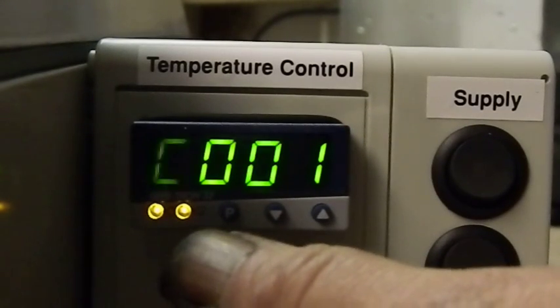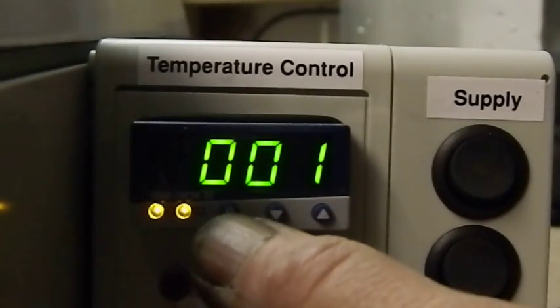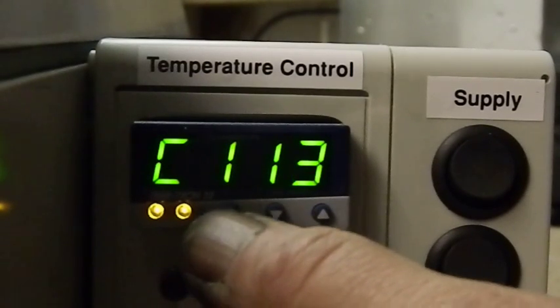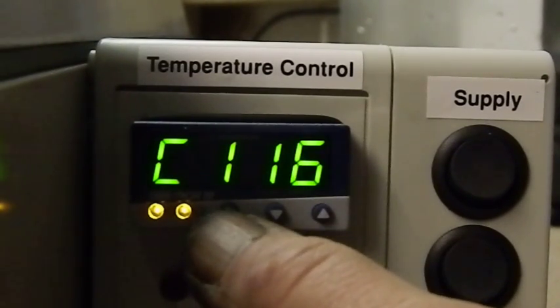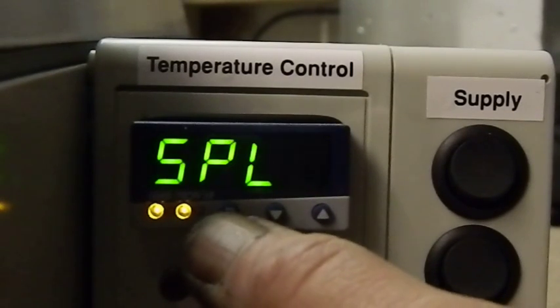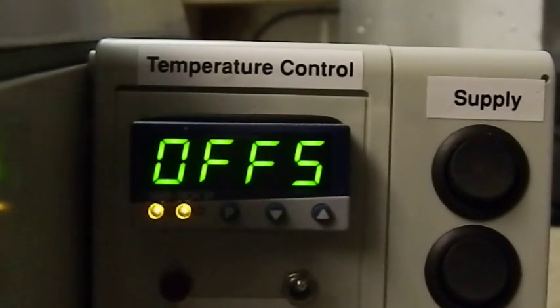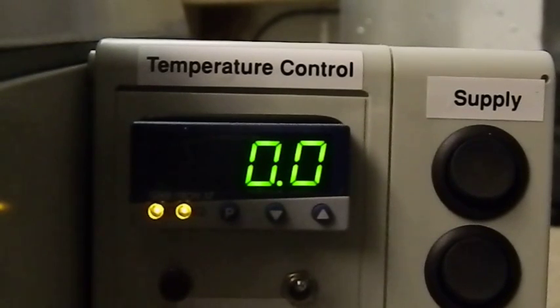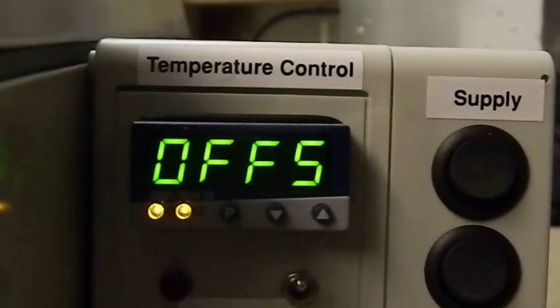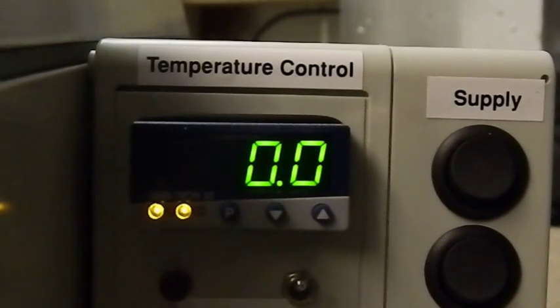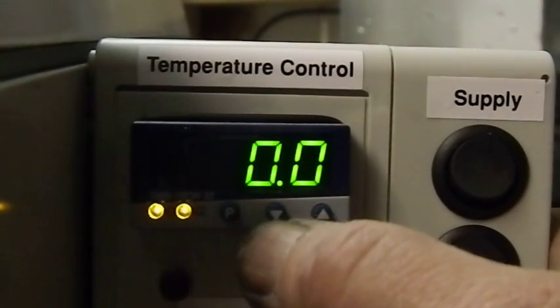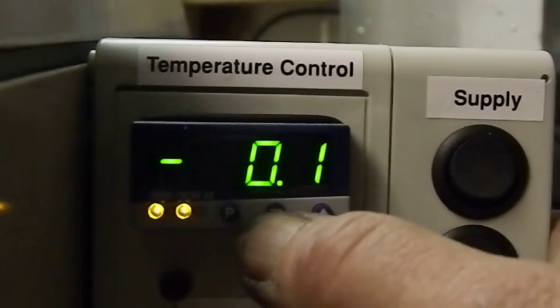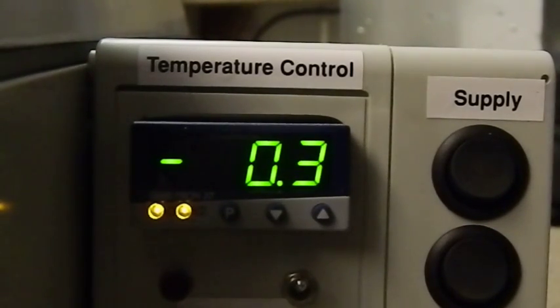This will take you through to C111. Again, we don't want to alter any of these parameters at the moment. Scroll through, pressing the P button a number of times until you get to OFFS. OFFS stands for offset, and it takes out the reading variation between your thermometer and the controller. Okay, so we know that the temperature inside the machine is 0.3 of a degree lower than the controller was reading, so we need to put in a minus figure to take the display value down by 0.3.